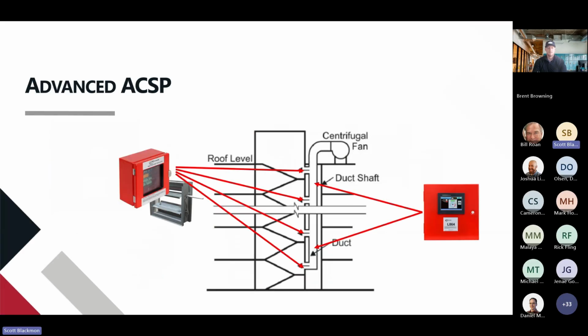And basically how that lines out is, if you'll remember, I said that we can do an injection point every 3 floors. Well, what we would do is have our L864 control the pressure inside the ductwork itself. And then at each of the injection points, we would have an 850 controller and an injection point damper. And that damper would open and close at that injection point based on pressure in that zone.